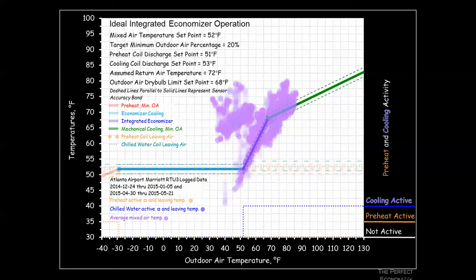Looking at the data, we see clouds of points in the upper left deviating from the ideal profile. This indicates the system is using minimum outside air in cases when it shouldn't be — returning to more energy-intensive return air instead of economizing — and likely keeping the cooling coil running in the 40 to 50 degree outside air range unnecessarily.